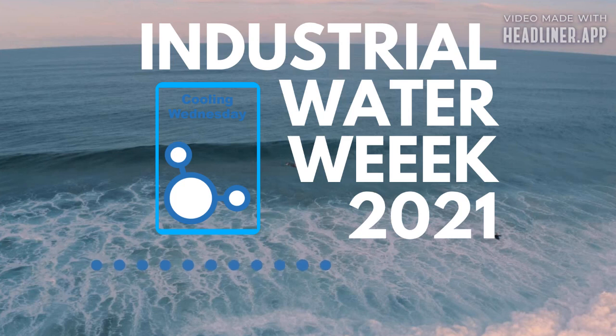Now, if we're just using bleed and feed, well, let's say we have a leak in the cooling tower. That controller is never going to see concentrated up water because we're never concentrating the water up because of that leak. So it's possible we never feed product into that cooling tower. So water meters are one of my favorite ways to feed product. And water meters are just a great thing to have on a cooling tower.